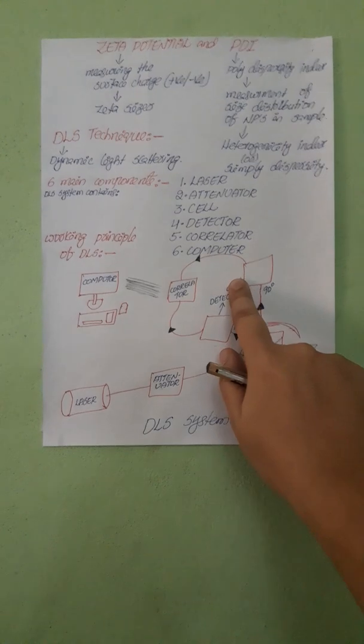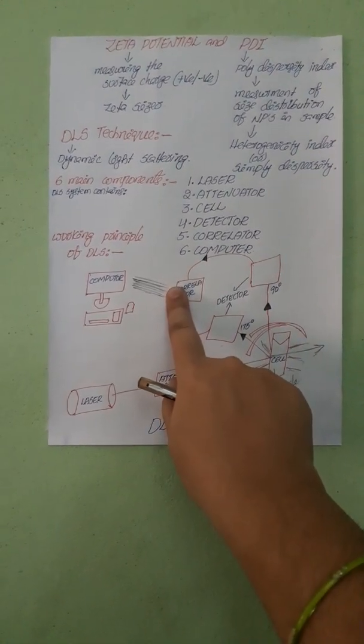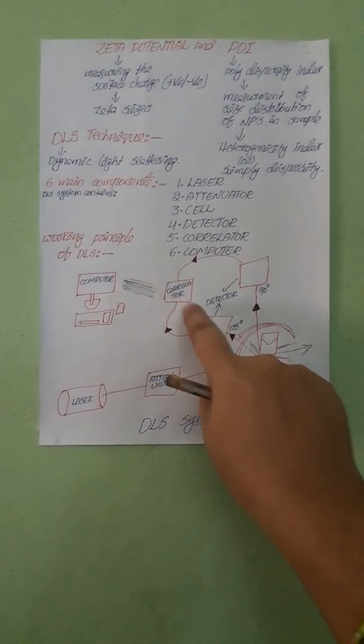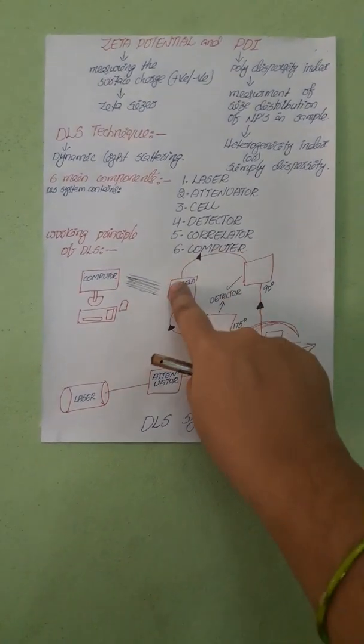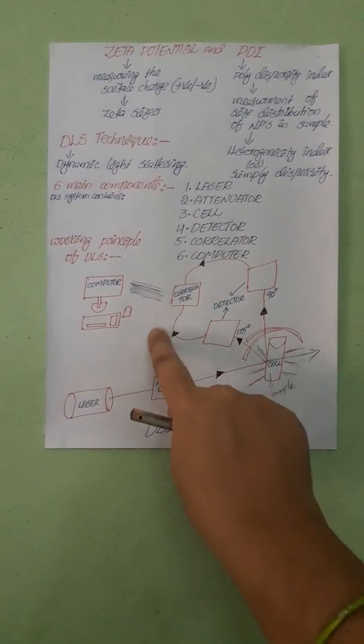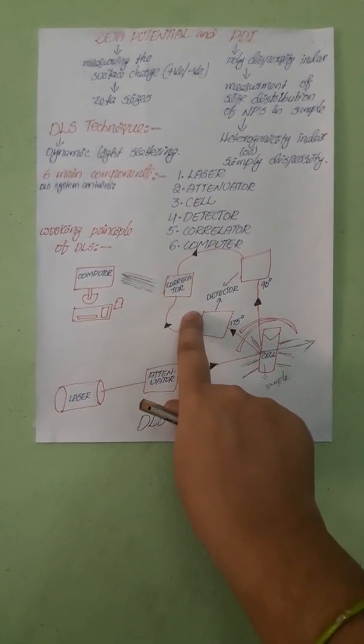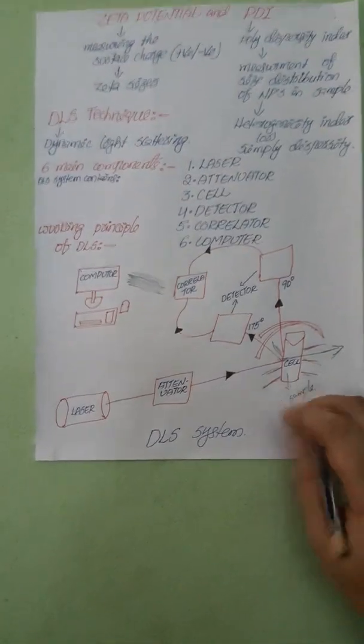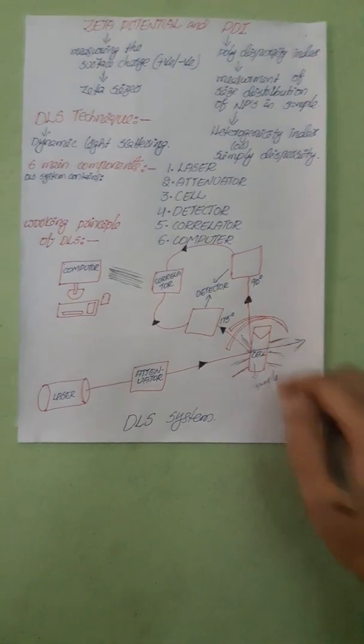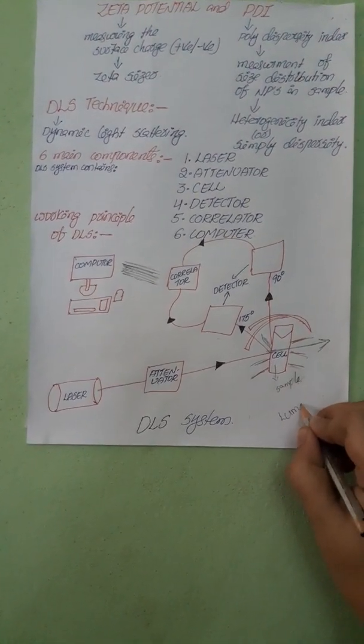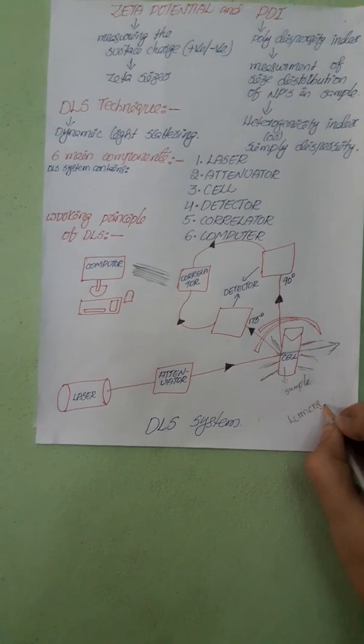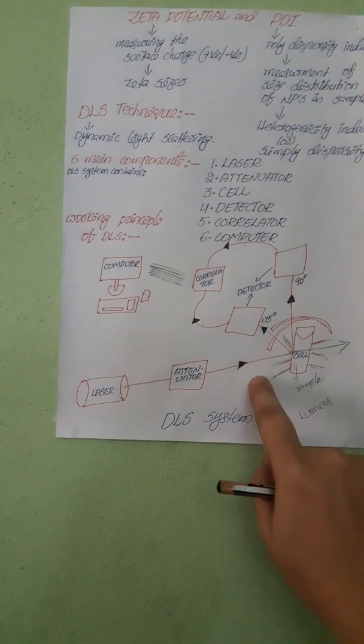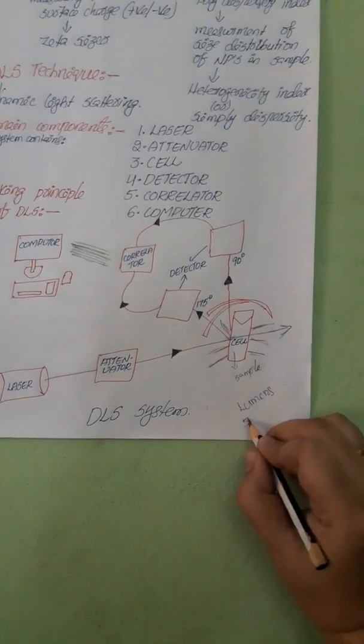The detector information will pass through a digital signal processing board, which is the correlator. The correlator compares the scattered light at successive time intervals. The intensity of the scattered light is measured in units of lumens, and the correlator correlates this scattered light based on time intervals.